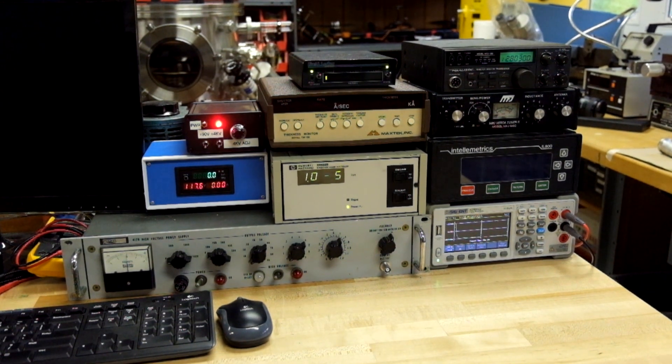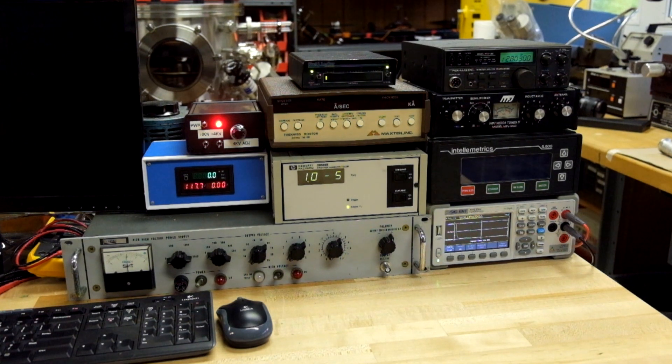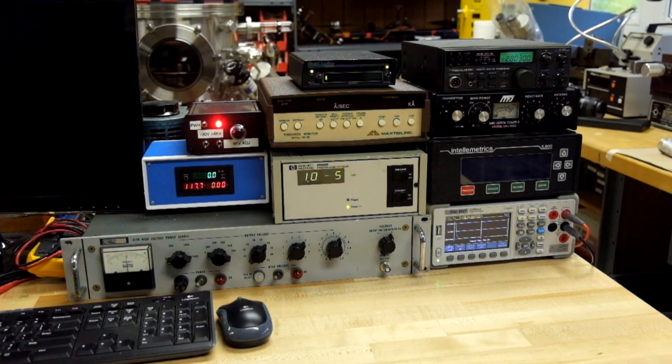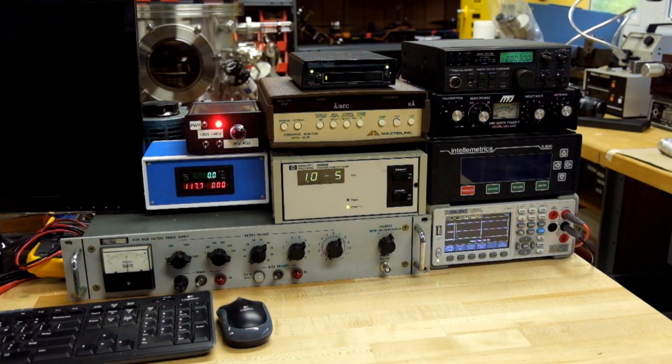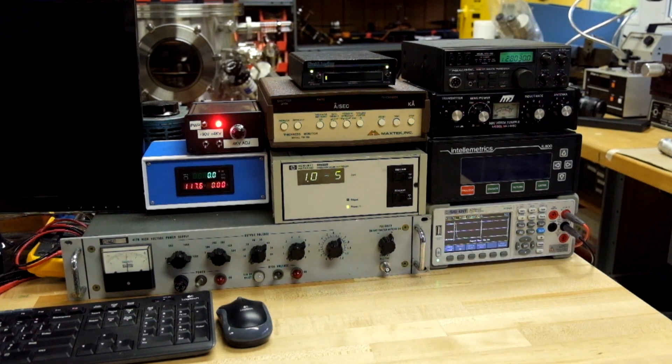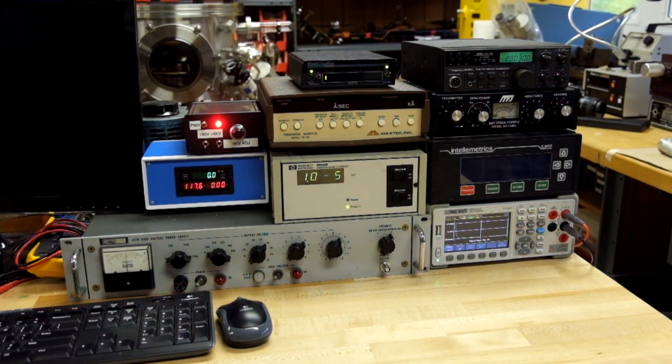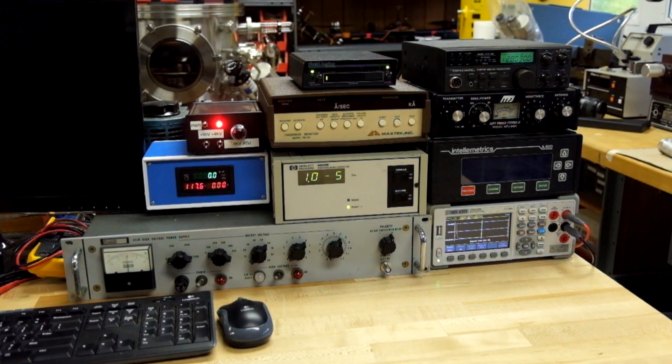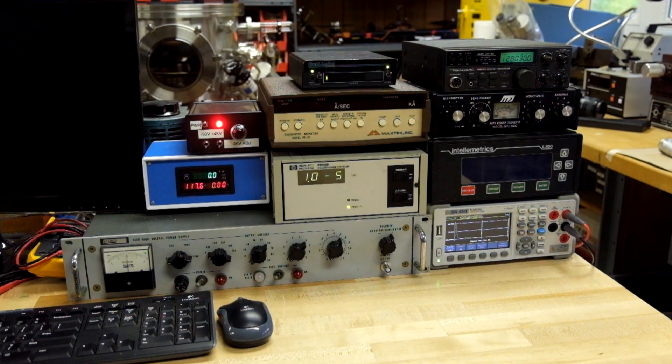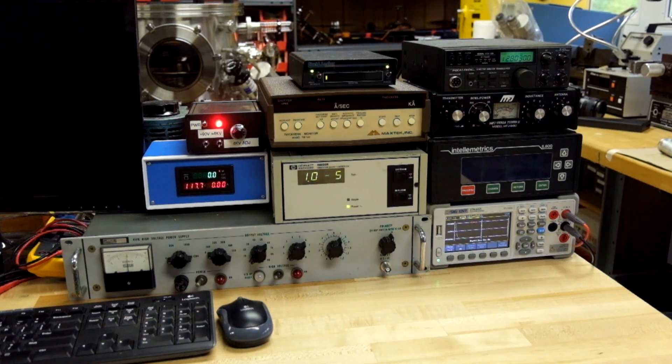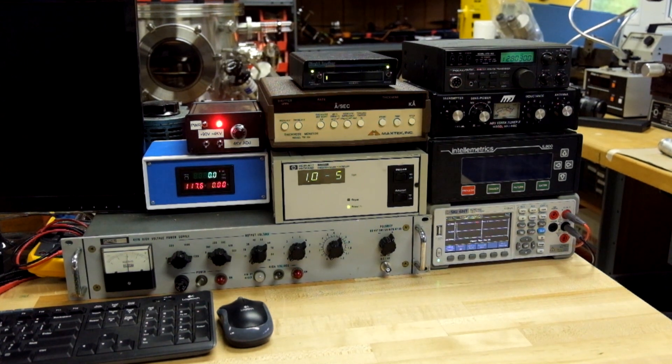That's all for this video. In a few minutes here, I'm going to turn off the turbo, turn on the mass flow controller. I'm going to flow some argon back into the chamber. I have some plasma experiments I want to do. And I'm going to do them around 100 millitorr or so. I can actually use the mass flow controllers to introduce argon into the chamber very slowly. And that helps brake the pump or slow it down. Right now there's very little friction for the blades. Magnetic bearings and there's no gas in there for them to collide with. So the pump can spin for hours after I shut the power off to it without dropping even 10 RPM.